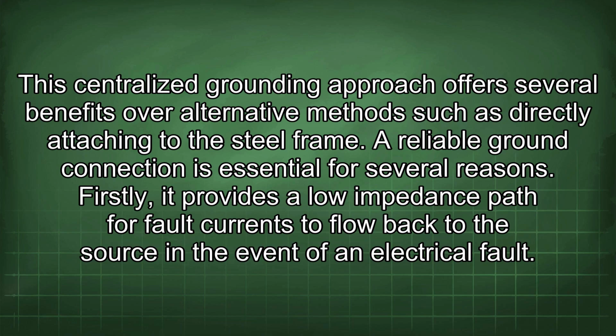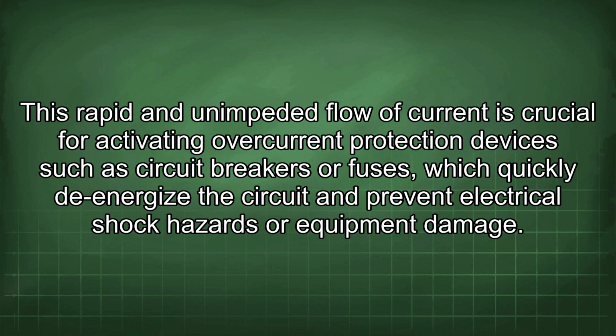A reliable ground connection is essential for several reasons. Firstly, it provides a low impedance path for fault currents to flow back to the source in the event of an electrical fault. This rapid and unimpeded flow of current is crucial for activating overcurrent protection devices such as circuit breakers or fuses, which quickly de-energize the circuit and prevent electrical shock hazards or equipment damage.